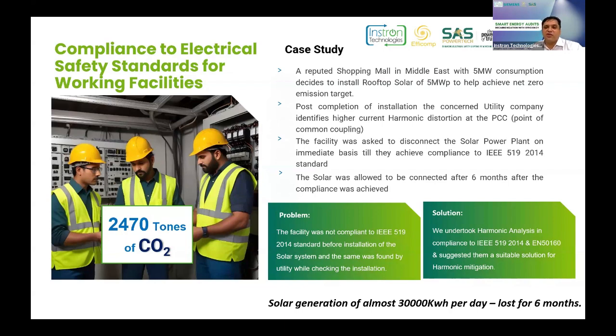The problem was that the facility was not compliant to IEEE 519 2014 harmonic standard even before installation of the solar system, and this was found by the utility while checking the installation. This was unfortunately not noticed, or maybe it was highlighted, but the shopping mall business guys did not pay attention to it.